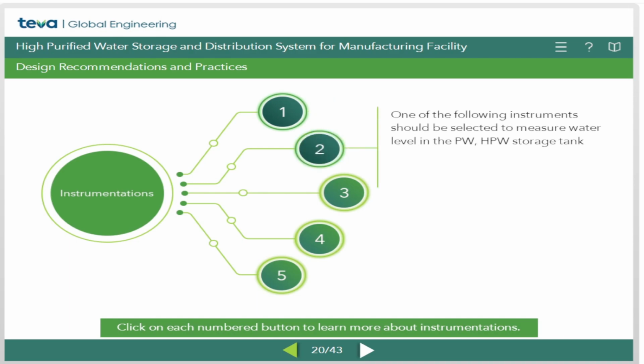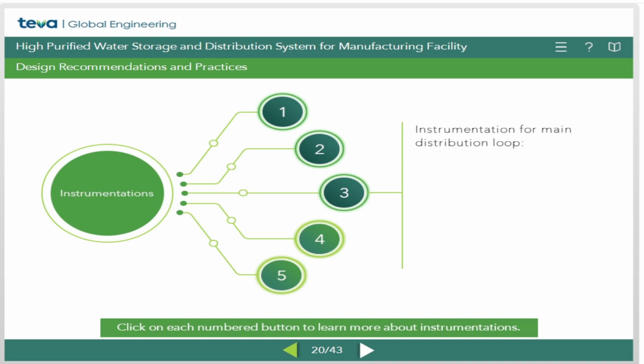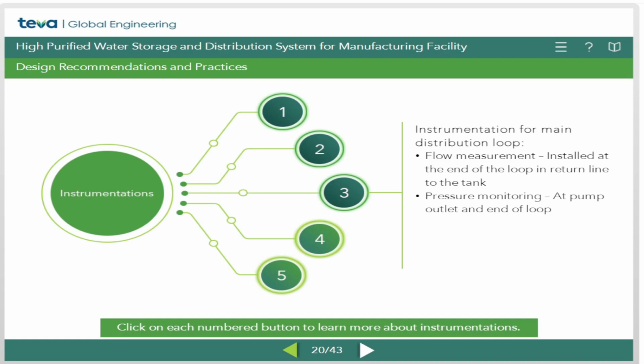One of the following instruments should be selected to measure water level in the purified water, highly purified water storage tank: load cells, guided radar, or balanced differential pressure. Instrumentation for main distribution loop: flow measurement, installed at the end of the loop in return line to the tank. Pressure monitoring, at pump outlet and end of loop. Temperature measurement, end of loop. Conductivity, end of loop. And TOC, end of loop.